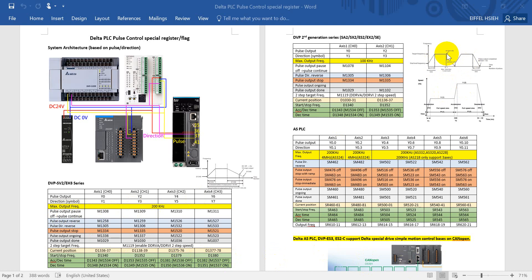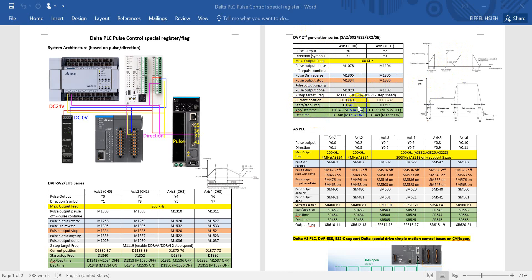For pulse output pause, you can see this figure. Once we turn on the signal, then the pulse output will stop or pause immediately. And once we turn off this signal, then pulse will continue output. But here it will stop with the target speed, let's say start or stop frequency over here.